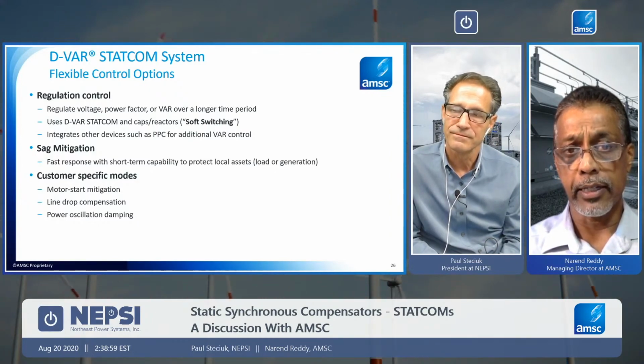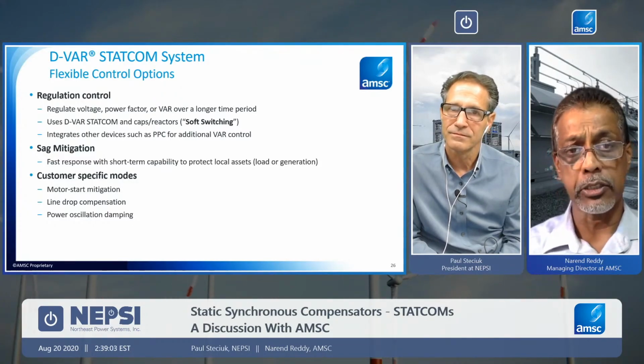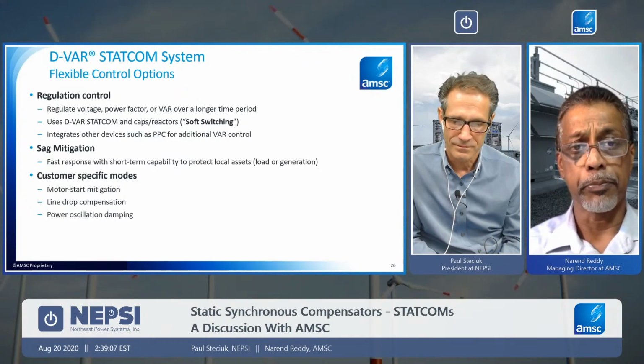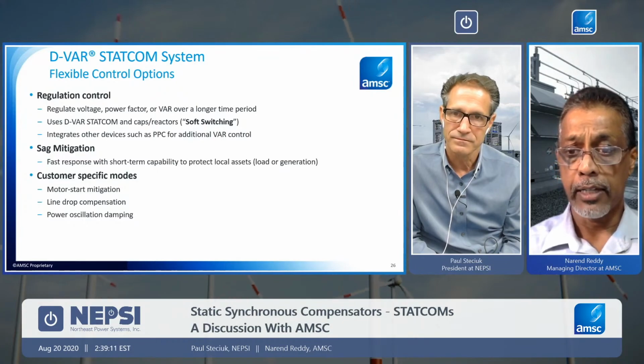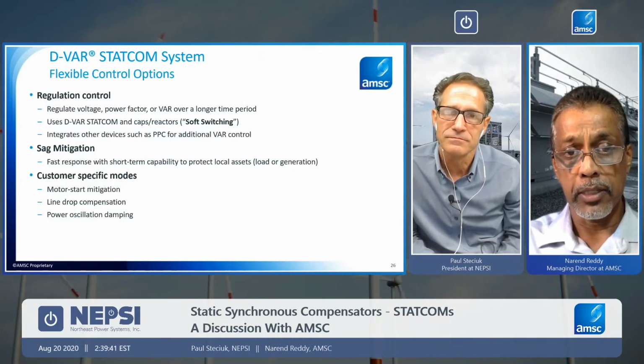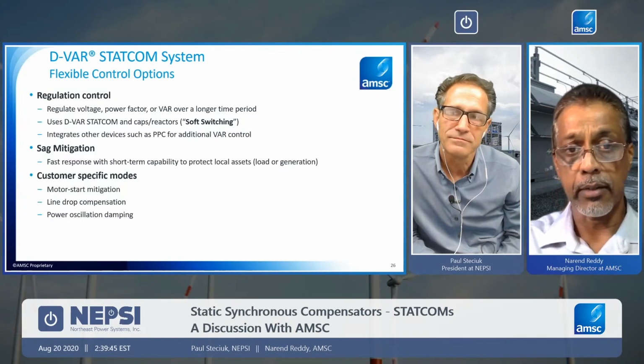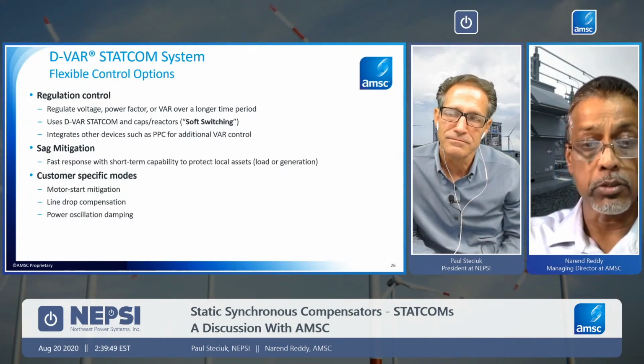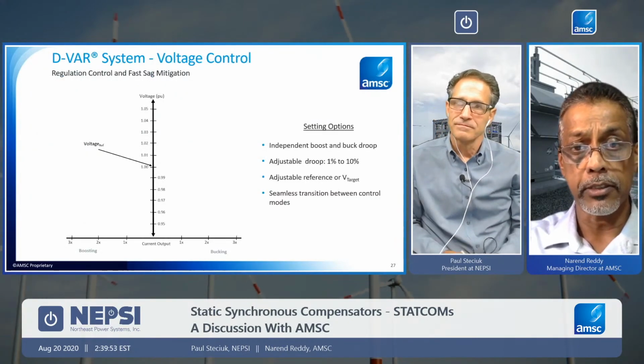Of course, we are able to integrate other devices. We have almost 2/3 of our applications, 120 of these applications, at renewable power plants. So we have developed controls that interface with power park controllers for additional vars, because these days those turbines and inverters have capabilities as well. For fast response and short-term capability, we've talked about using overload for those. In addition to that, we've sold over 185 systems around the world, which has allowed us to look at a lot of different application needs and types. So there's been a lot of controls development to meet those requirements. There's a couple listed in here, and there are numerous that we can do. Any new systems going out have the benefit of all of these controls being available.